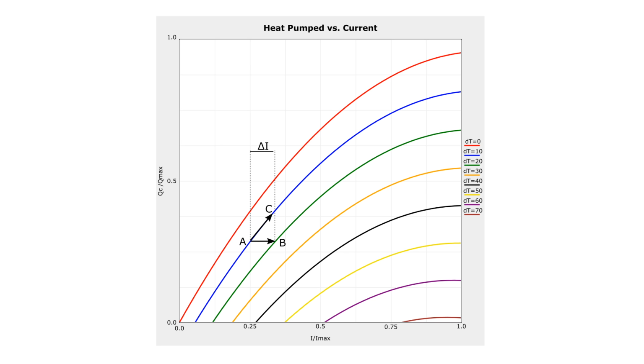If we operate the Peltier element with a current around 25% of Imax, it is possible to compensate a rise of delta T from point A to B by increasing the current. The heat pump capacity stays unaffected. The heat pump capacity can be increased as well without changing delta T if we move from A to C.